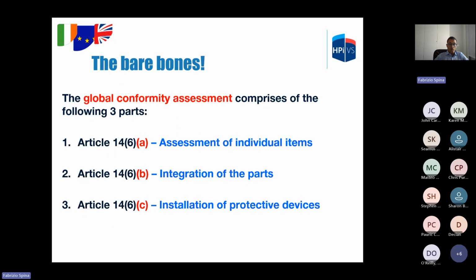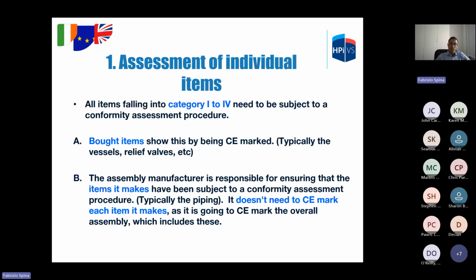The main structure of the global conformity assessment. The global conformity assessment is made of three main steps: the assessment of individual items, the integration of the parts, and the installation of protective devices. The first step is the assessment of the individual items. So all items falling into category 1 to 4 need to be subject to conformity assessment procedures. The category definition is based on the equipment type, vessel, piping, or boilers, the fluid, flammable or non-flammable, gas or liquid, and the combination of pressure and volume. The PED includes 9 tables in Annex 2 for this classification.